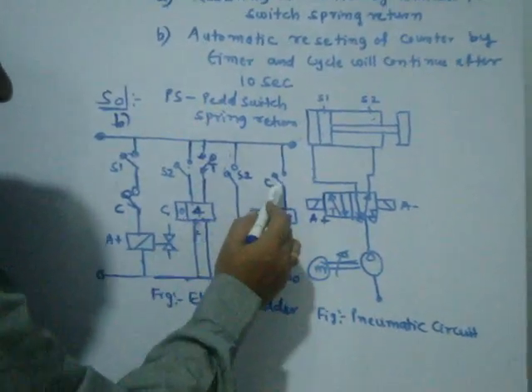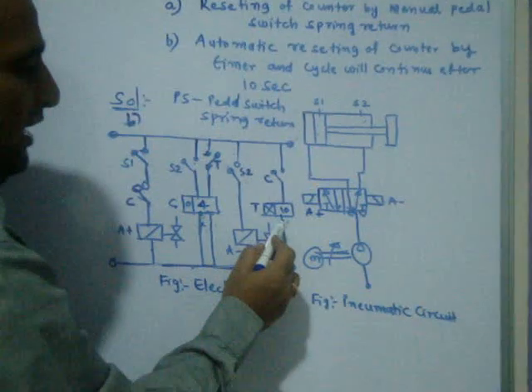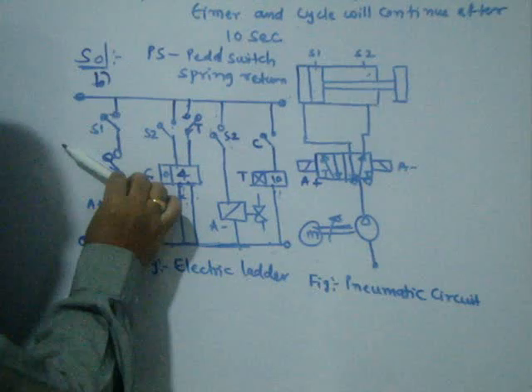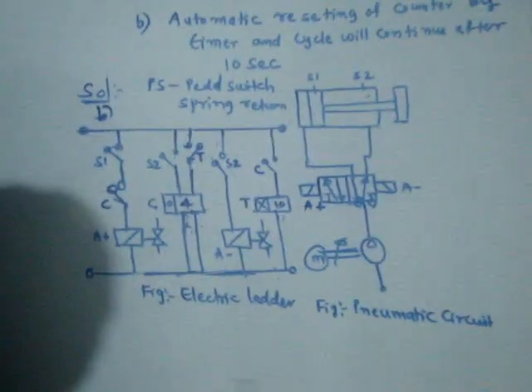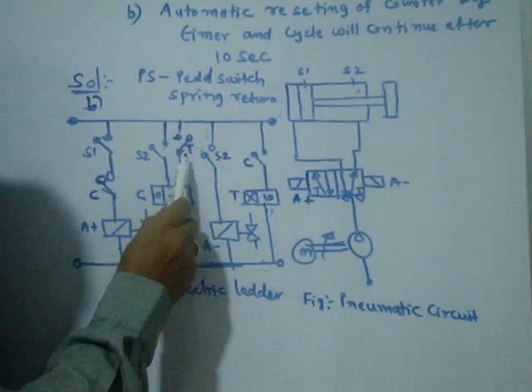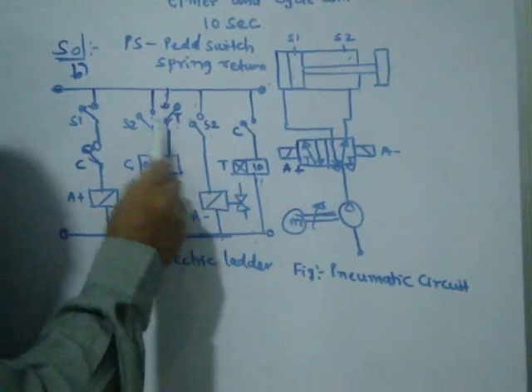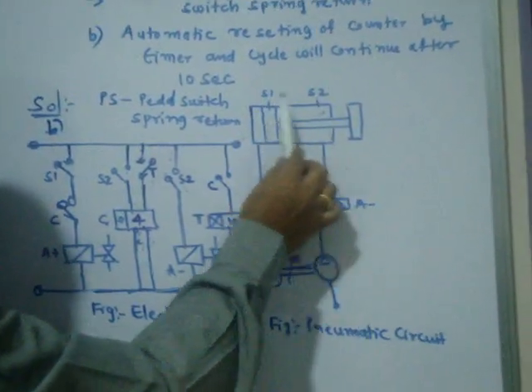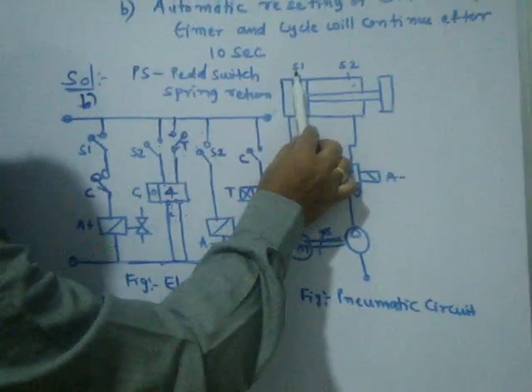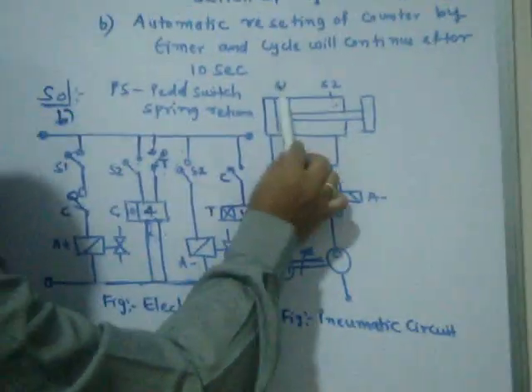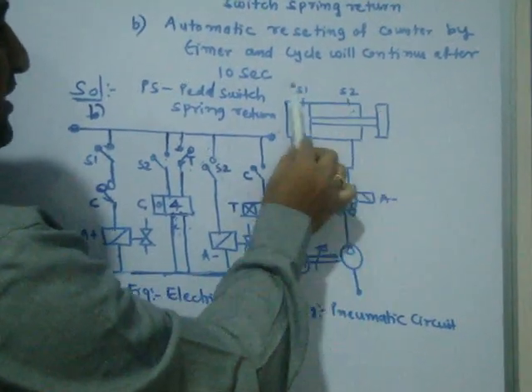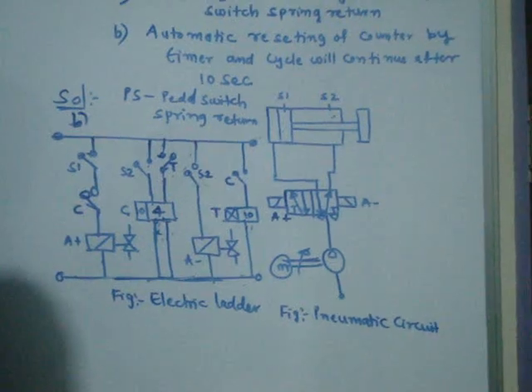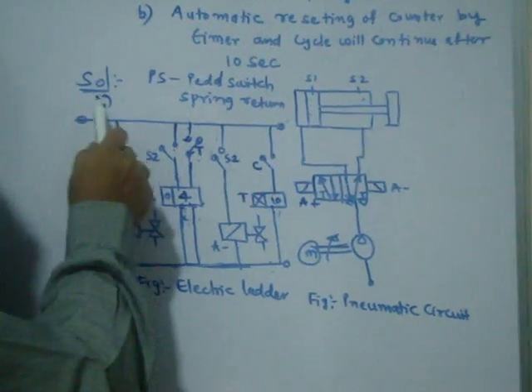When the counter turns off, the timer will also turn off. And this normally closed contact, which was open when the counter was on, now closes — the second cycle starts. This is resetting by on-delay timer — everything is automatic. So it goes 1, 2, 3, 4, stops for 10 seconds, then 1, 2, 3, 4 again. Everything is automatic for B bit.